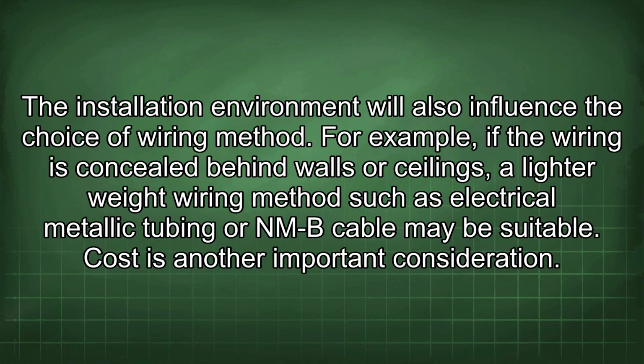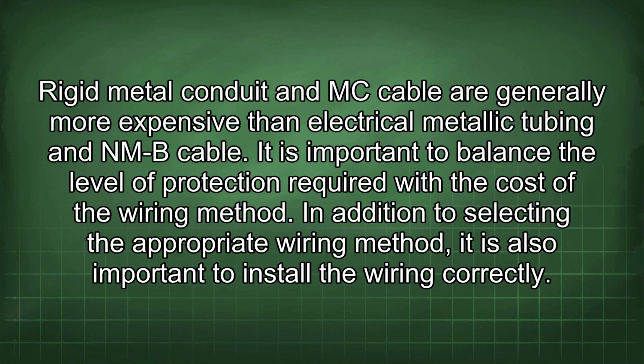The installation environment will also influence the choice of wiring method. For example, if the wiring is concealed behind walls or ceilings, a lighter weight wiring method such as electrical metallic tubing or NMB cable may be suitable. Cost is another important consideration. Rigid metal conduit and MC cable are generally more expensive than electrical metallic tubing and NMB cable. It is important to balance the level of protection required with the cost of the wiring method.